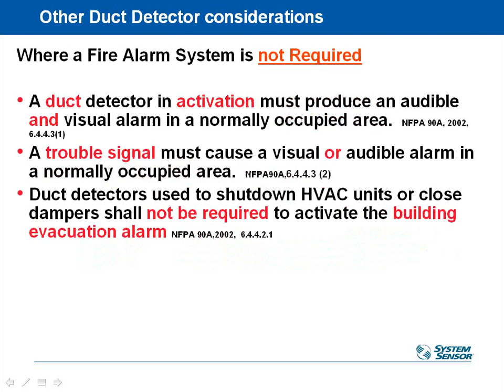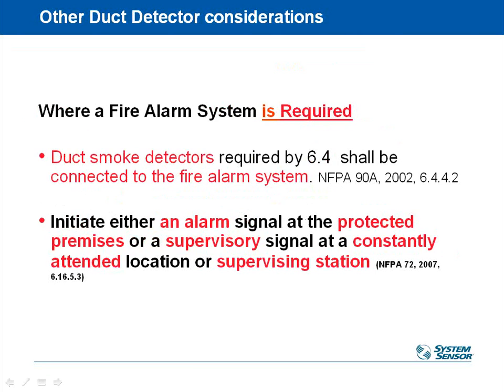If you don't have to have it because of code and you're just putting it in because you want to, then you don't have to necessarily integrate the two together. So you don't always have to have the duct detectors tied into the fire alarm system. In fact, most systems, the duct detectors are standalone. But there are some types of buildings, specifically larger high-rise buildings, that NFPA requires you to have a fire alarm system, and then it goes ahead and requires you to integrate it to the duct smoke detectors.